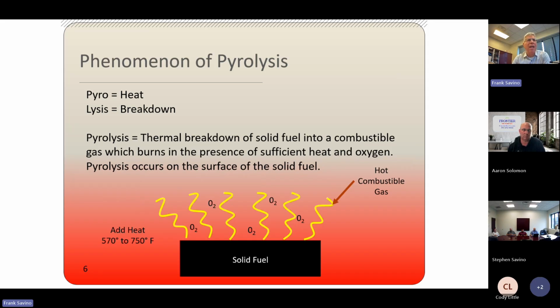Okay, so the phenomenon of pyrolysis. The word pyrolysis comes from the Greek words pyro, which means heat, and lysis, which means breakdown. Pyrolysis occurs on the surface of a solid fuel. So if you take a piece of solid combustible material, a piece of wood, a piece of cardboard, a piece of plastic, and you heat that solid material to between 570 and 750 degrees Fahrenheit, it'll start to form hot combustible gases that will off-gas from the surface. Sometimes you can see that if you put wood or cardboard near a hot surface: you'll see smoke coming off of it even though it's not burning. That smoke is actually combustible gases. If you combine that hot combustible gas with oxygen, which is in the air, and heat, you will get fire.